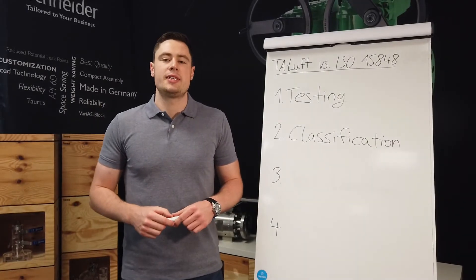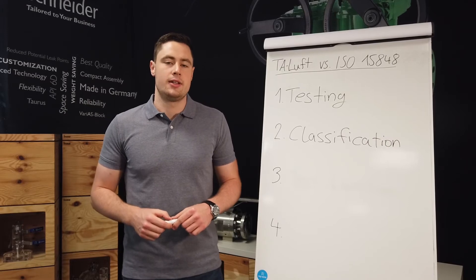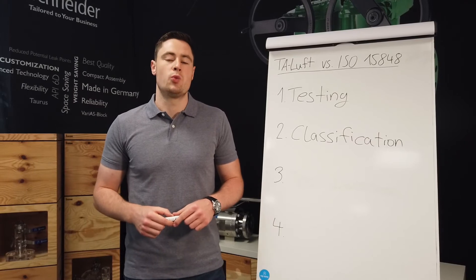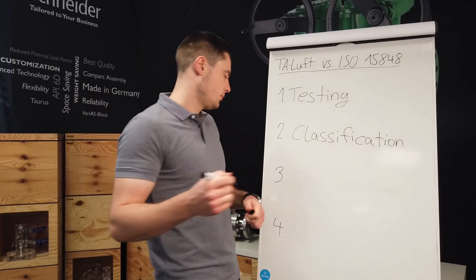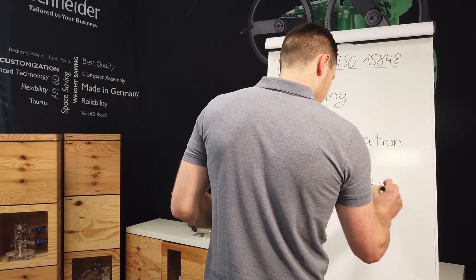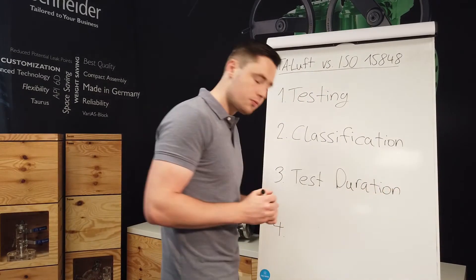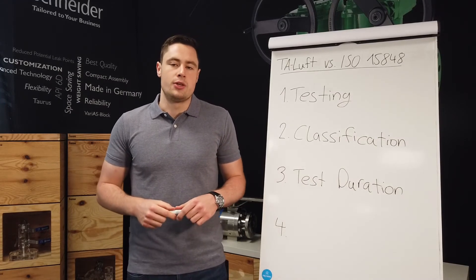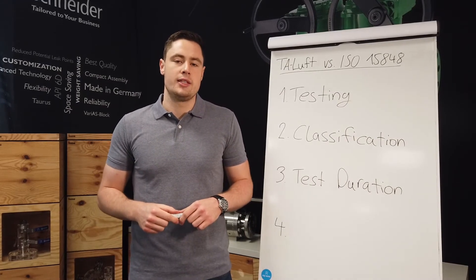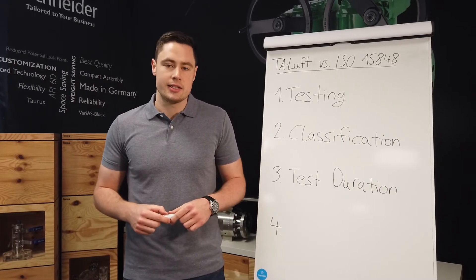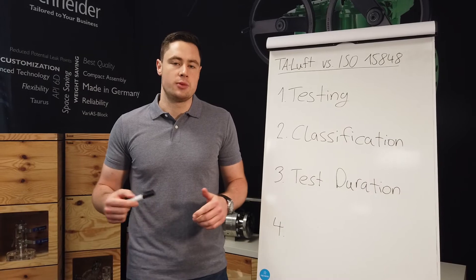The requirements of the ISO type test are very specific and detailed. As a result, the test duration for a complete ISO 15848 type test takes one to two weeks. The requirements of TA-Luft are very general. The duration of a TA-Luft test normally does not take longer than one to two days. There is no requirement for either the number of mechanical cycles or the number of thermal cycles.